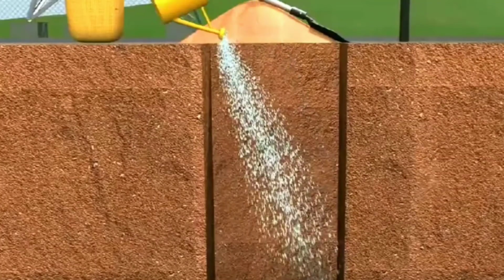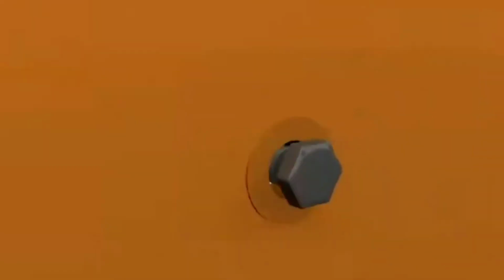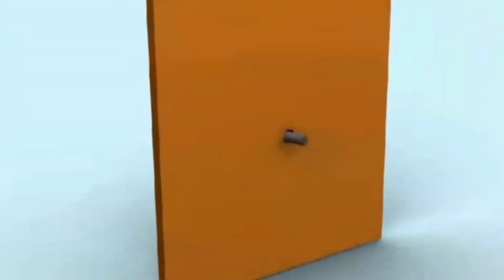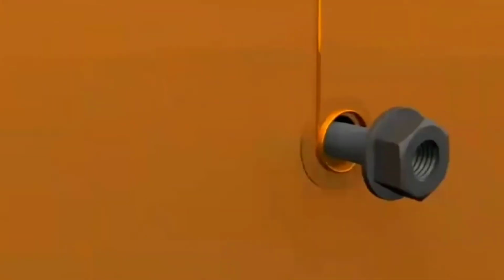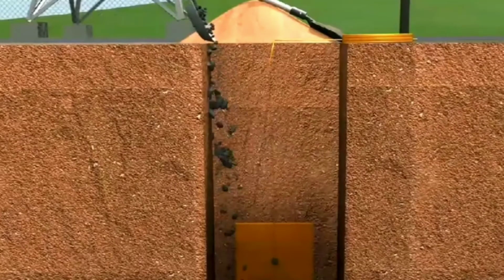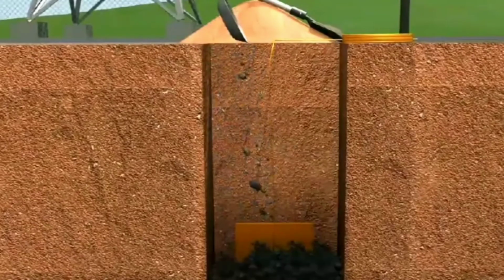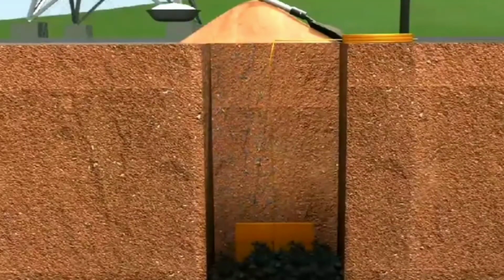Sufficient quantity of water is sprinkled on the bottom and surrounding walls to make them wet. The bottom layer of the pit is filled with a mixture of black soft soil and charcoal pieces. An appropriate copper plate is buried in the pit in a vertical position. Earth lead is tightened with nut bolts to the earth plate. A layer of powdered charcoal and lime mixture is filled around the earth plate. This action makes better continuity in the earth and also helps to maintain the moisture condition.